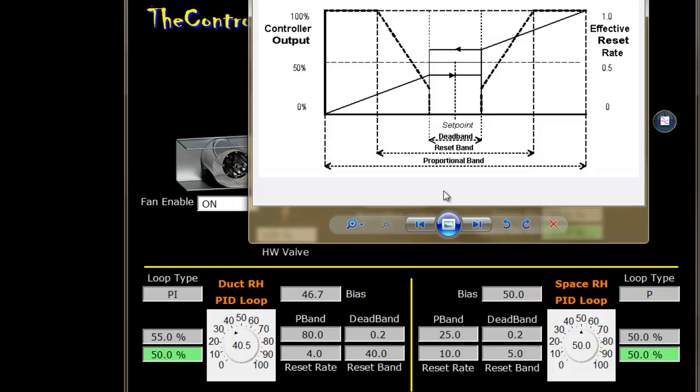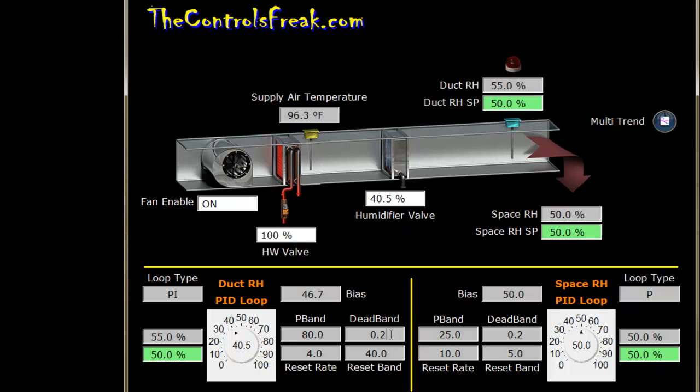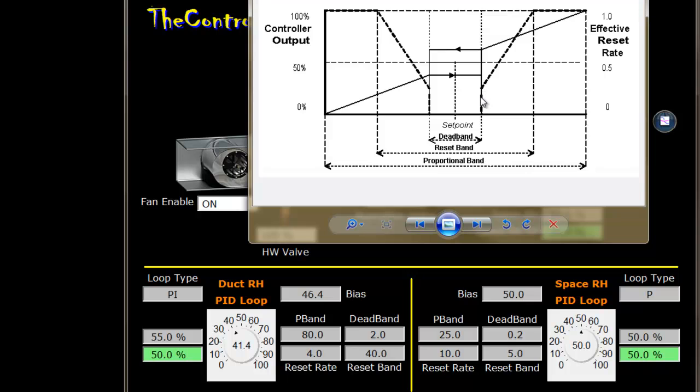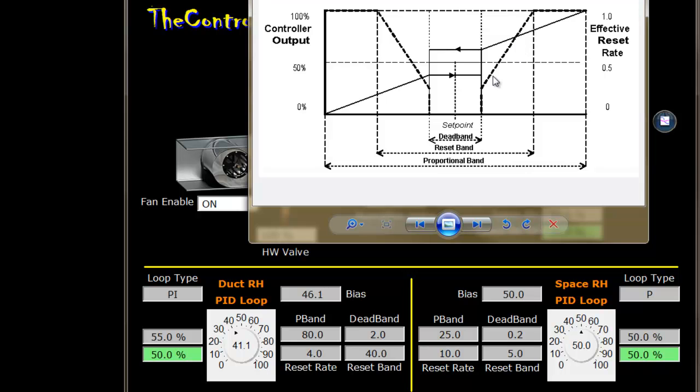The dead band pretty much kills the proportional and integral. Earlier we used 0.2, but I'm changing this to 2. Once I hit within 1% of set point—because the 2 represents both sides of set point—I'm going to say I'm not going to adjust the CO loop percentage regardless of proportional band or reset. That's how the integral proportion slides depending on distance from set point.